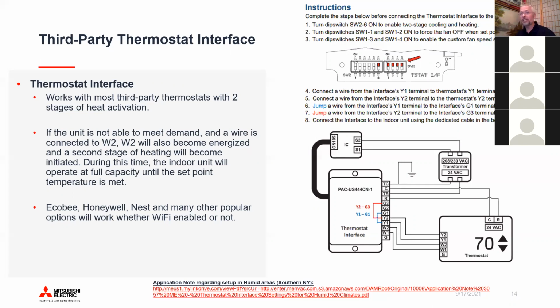And will it work? Absolutely. May it be appropriate for ducted solutions? It might be appropriate for ducted solutions depending on the layout of the ductwork and what you're trying to accomplish. But most of the time, when you're doing a third-party thermostat interface, you're going to want to have 2-6 on so that the Mitsubishi equipment can modulate and match the temperature and provide all of the efficiency through its controls that you would expect out of Mitsubishi equipment. Okay. The other control switch, switch 1, has 4 dip switches.